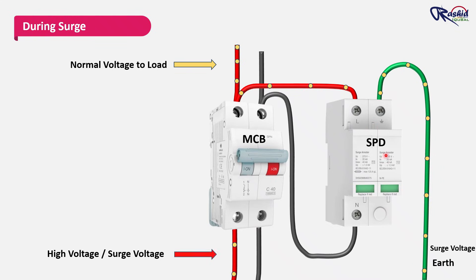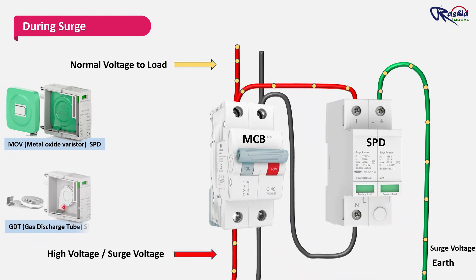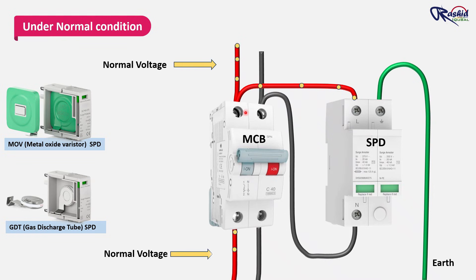Inside the SPD, there are two main types of protective parts: the metal oxide varistor, called MOV, and the gas discharge tube, called GDT. MOV reacts fast and reduces the voltage, while GDT works like a small spark gap to discharge big surges. Both types are designed to keep the extra voltage away from your equipment. They quickly switch on during surges and switch off again once things return to normal. This whole action happens in microseconds.